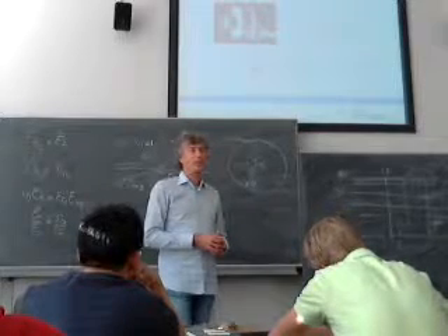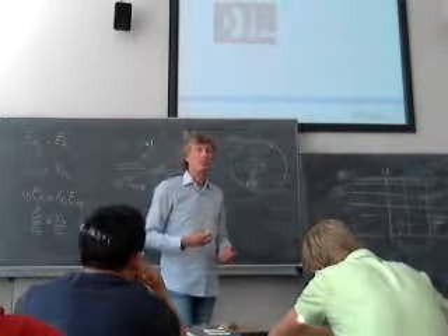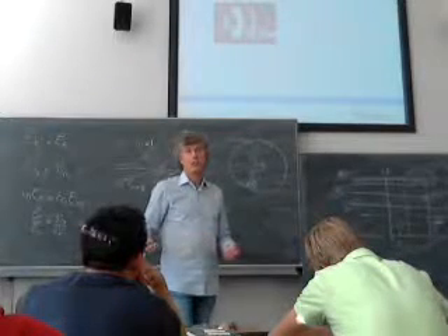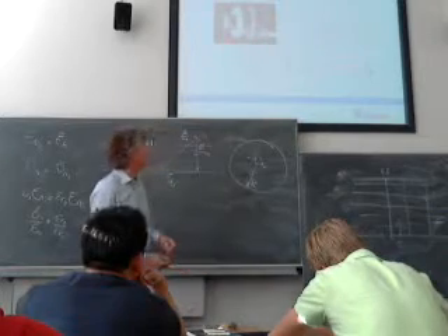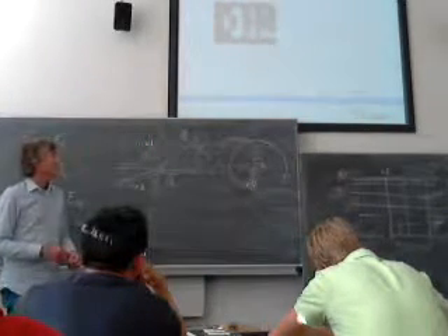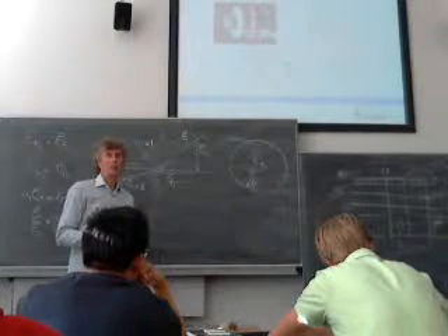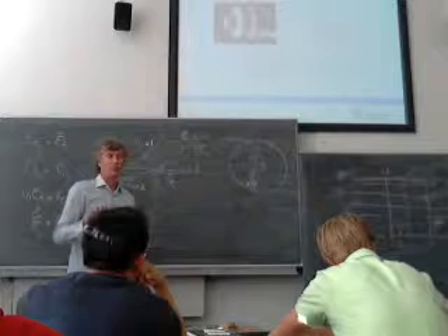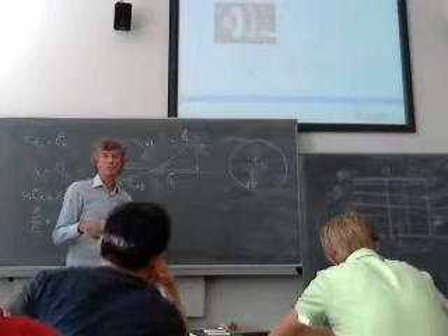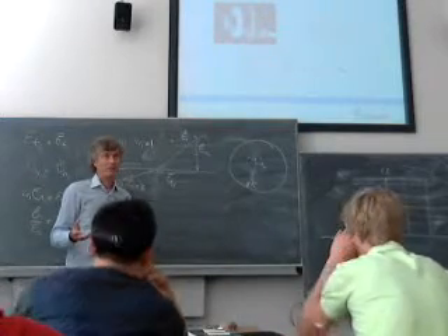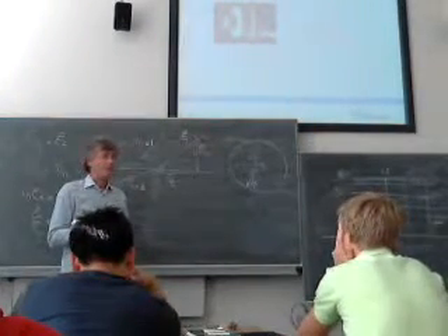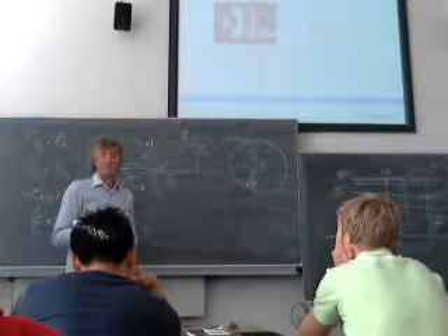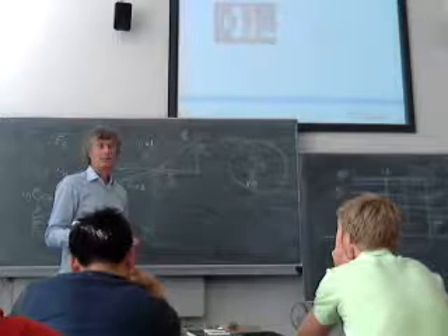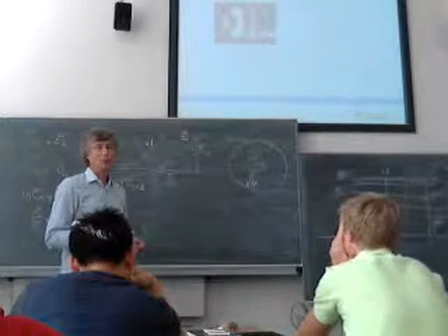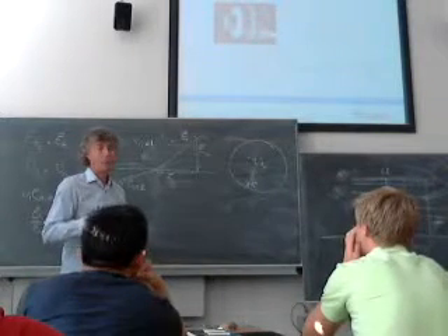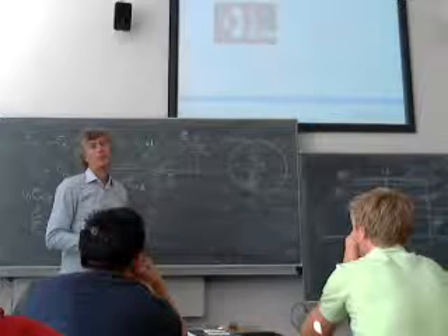To avoid breakdown, because the higher the electric field, the higher the electric stress in the material, so more aging and it becomes weaker. But there's also another reason: suppose in a situation where we have a really high field in the insulation, there's also a cavity, a manufacturing defect, a gas-filled cavity. Well, then we're in bad shape, because the electric field will be enhanced by a certain factor. Let's say the factor is epsilon. For polyethylene, high voltage cable, epsilon is 2.3. So we would have an electric field which is already high, enhanced by a factor of 2.3, in a medium that is very weak.